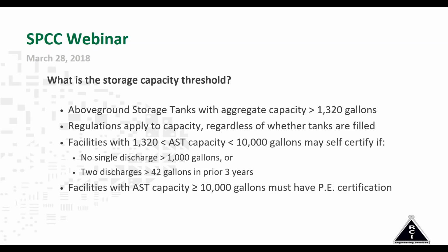If your combined capacity is less than 10,000 gallons and you haven't had any single discharge over 1,000 gallons or two or more discharges over 42 gallons in the prior 3 years, then you are eligible to self-certify your SPCC plan.